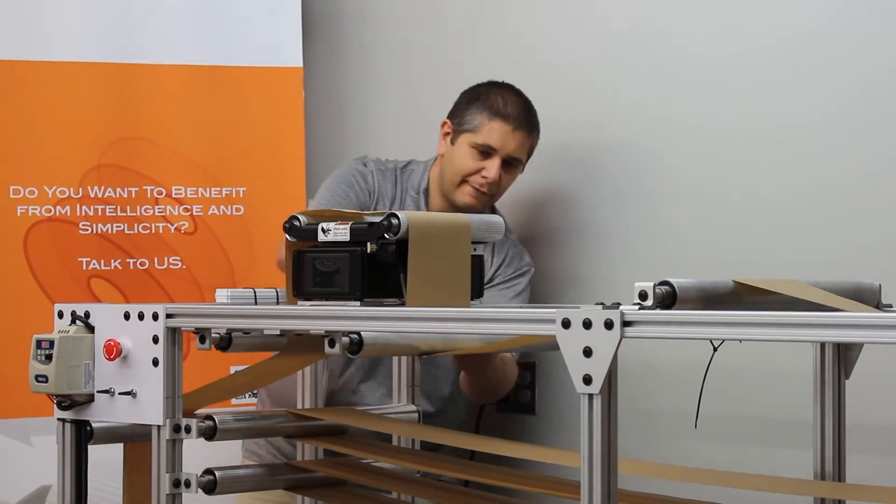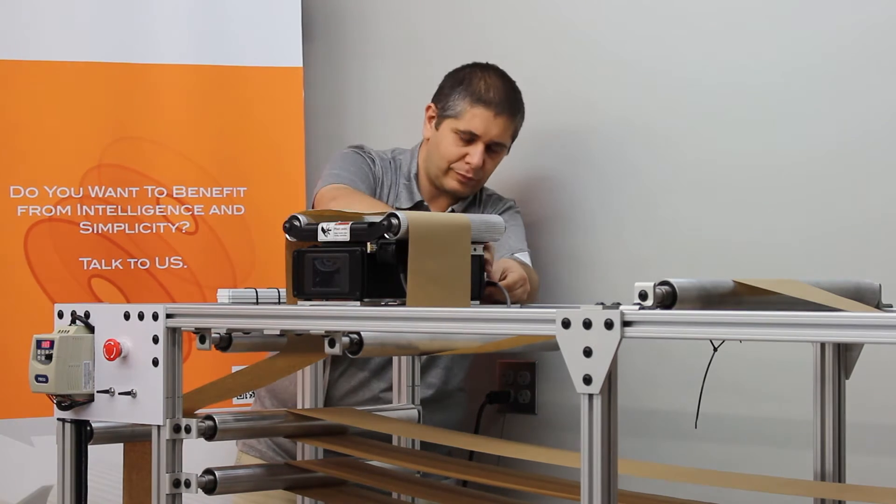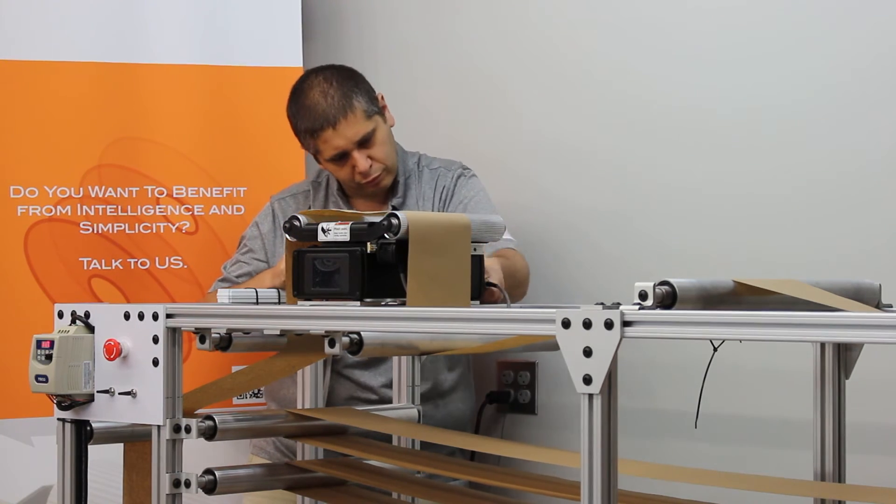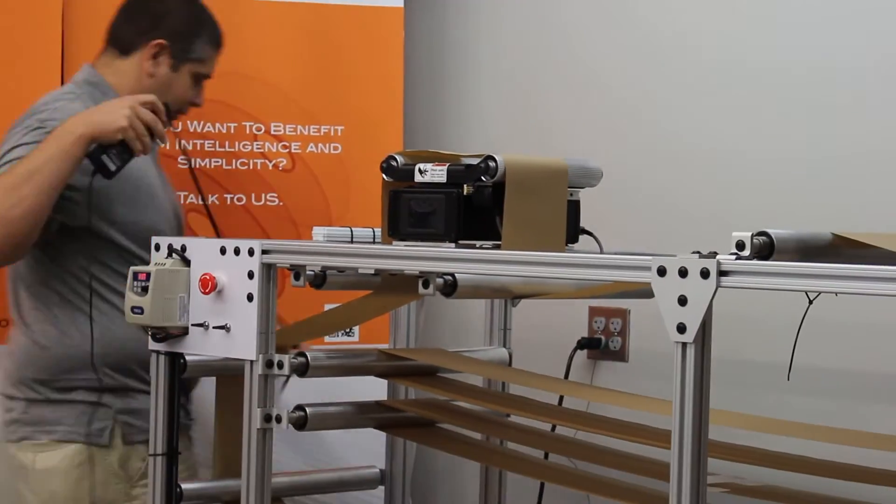Use the thumb screws to secure the sensor to a desired position. Using the 12-pin DIN connector on the sensor cable, connect the sensor to the web guiding system. Make sure to thread the sensor connector all the way through to secure it in place.